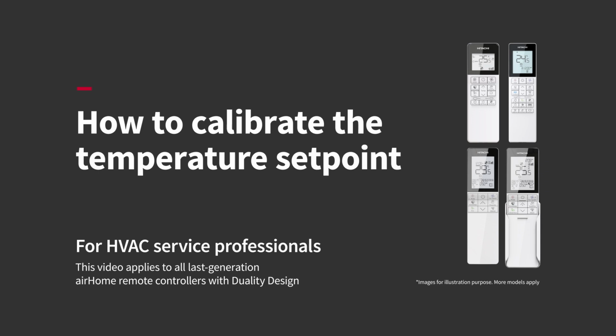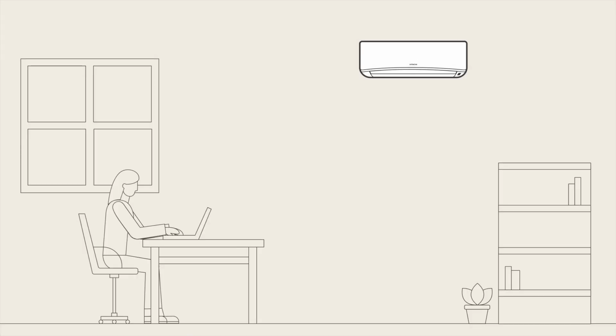Hi friends! To all HVAC professionals, contractors, installers, and service providers, let's find out together how to calibrate the temperature set point of airHome heat pumps to improve occupants' comfort. Before showing you how to do it, let us remind you that temperature calibration allows you to adjust the set point entered by users by a few degrees when the AC cannot accurately read the temperature surrounding the occupants, due to temperature differences within the room itself.